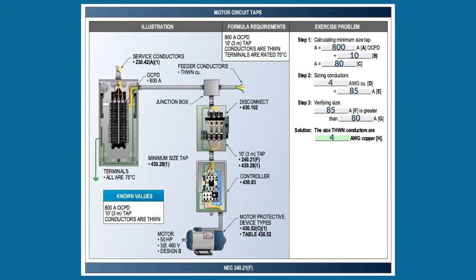But now when I look at sizing for this motor, the conductors coming down, I've got to make sure that this is the minimum, but I got to make sure what size I need for that motor. So if I go look at 430.22 for a single motor, I'm going to take that 65 amps at 125%. That's going to give you roughly 81.25 amps, which a number 4 would be the exact size that was needed for that tap. And that pretty much is how easy taps are.